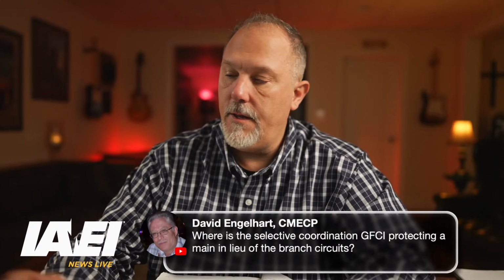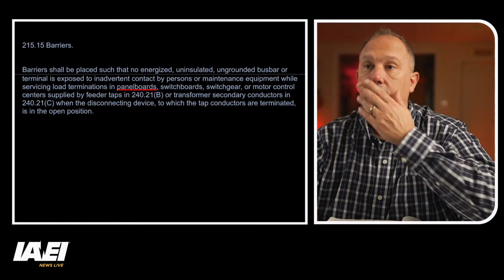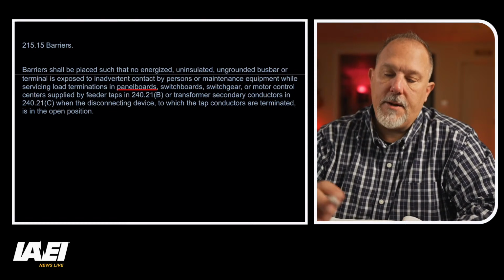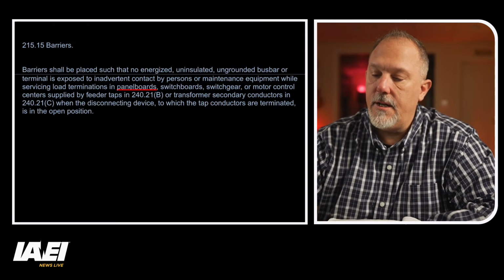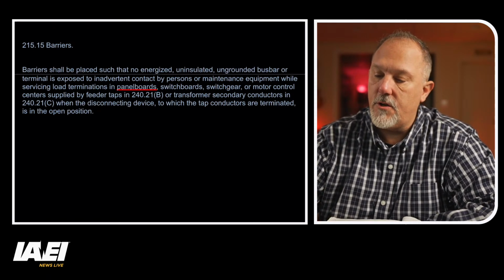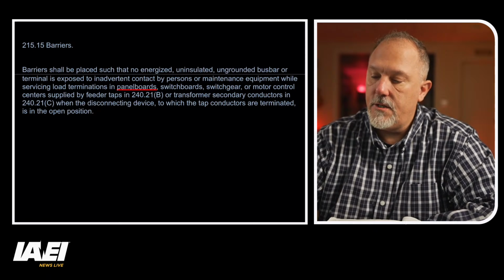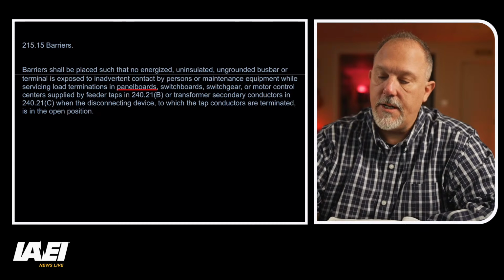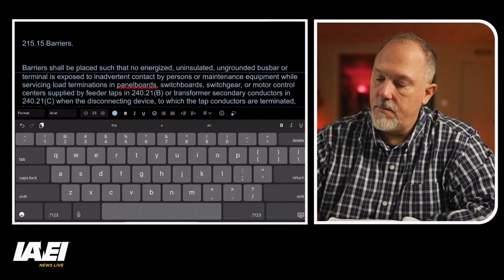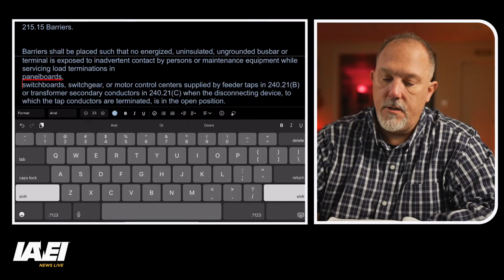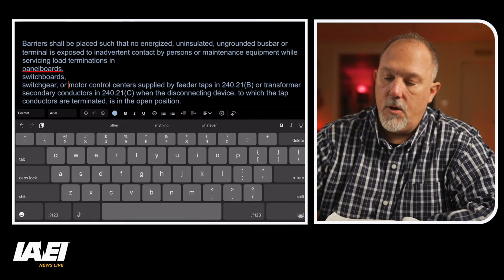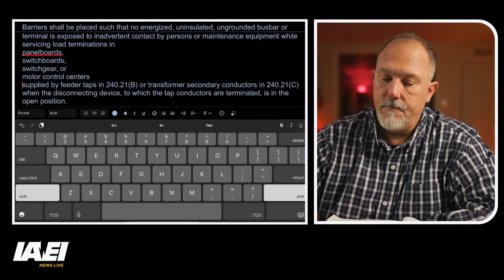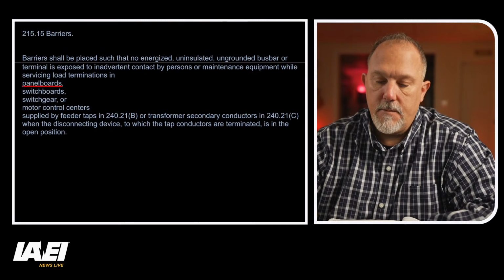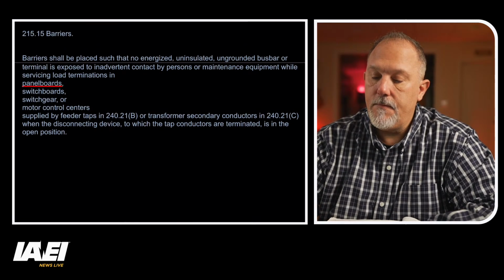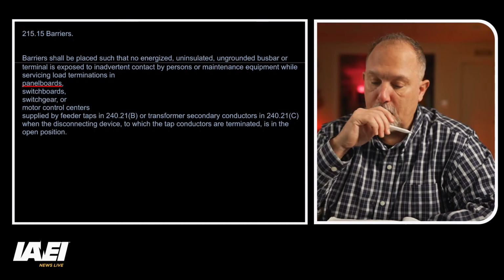All right, so here is the language. Barriers have to be placed. No energized, uninsulated, ungrounded busbar or terminals exposed to inadvertent contact by persons or maintenance equipment while servicing load terminations in panel boards, switchboards, switchgear, or motor control centers supplied by feeder taps or transformer secondary conductors.